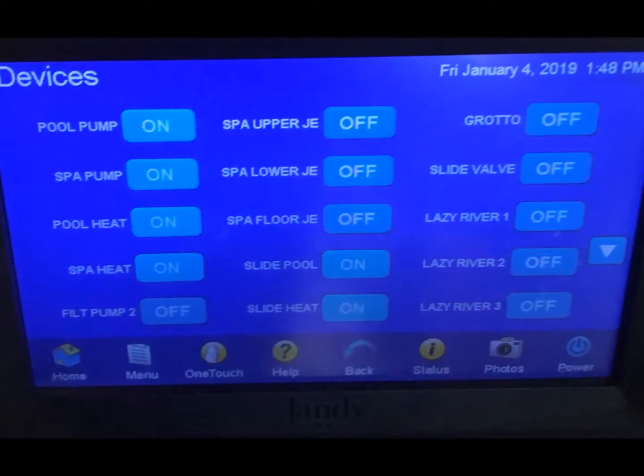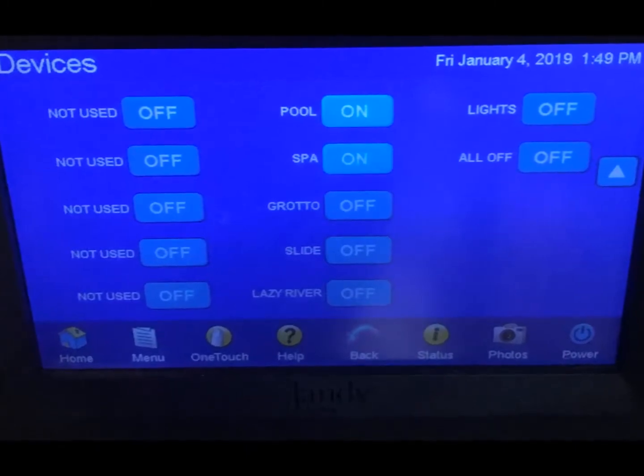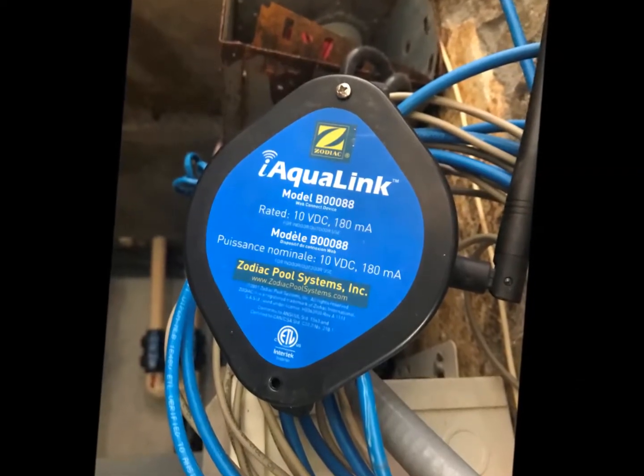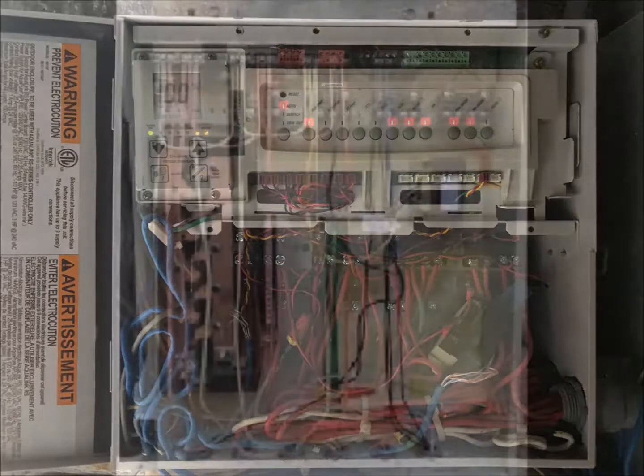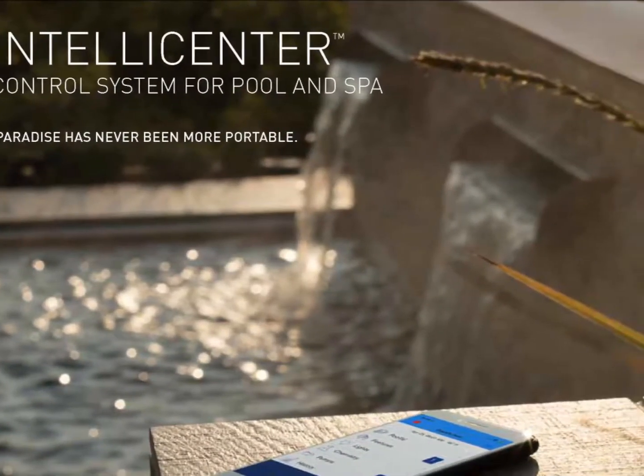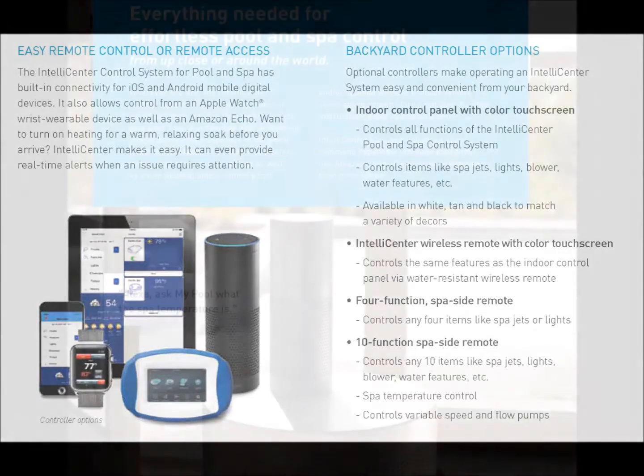Besides the pumping, filtering, and plumbing inefficiencies, there have been some issues involving the control system's operational functionality. In viewing the electrical subpanel, I observed missing cover plates and a spider web of exposed wires that could be a source of bad connections. This would require some time to diagnose and solve, or as an option, a retro-update wireless web-accessible hardware system could be installed — upgrading might be a better use of time and money. During the past six years since the pool was constructed, technology has advanced and artificial intelligence has made a better connection with convenience as a fully vested partner.